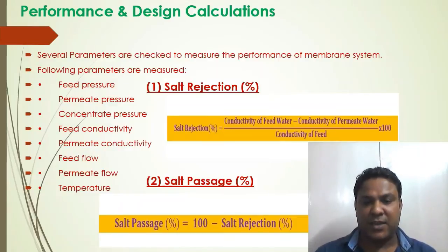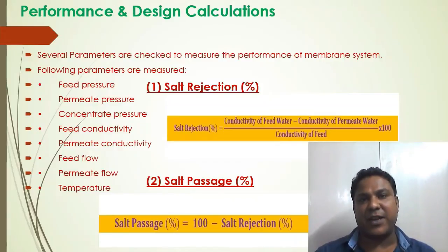It doesn't tell how each individual membrane is performing, but rather how the system overall, on average, is performing. A well-designed RO system with properly functioning RO membranes will reject 95 to 99% of most feedwater contaminants.